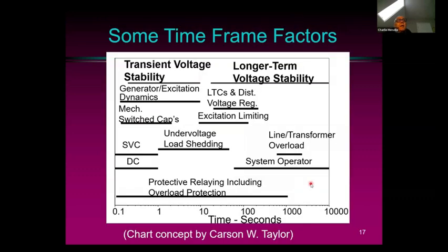These are some of the phenomena that can and have happened in various power systems that affect their stability under conditions of low reactive power. This time frame starts at 100 milliseconds, and some of these things are very fast, like DC controllers and static VAR compensators. Switched shunt capacitors take a little bit of time, maybe 200 milliseconds to come into service. Generators and excitation dynamics: generators can increase their reactive power output.